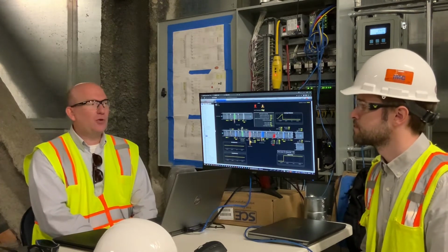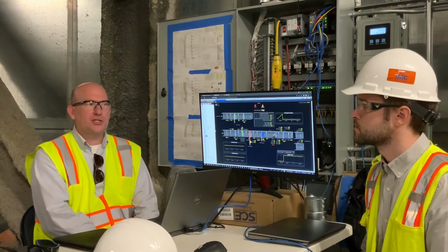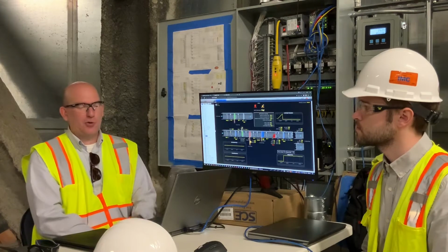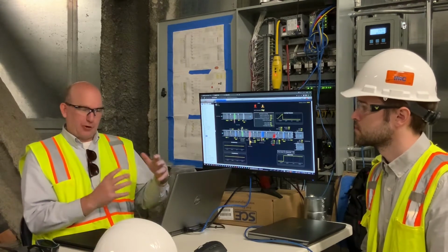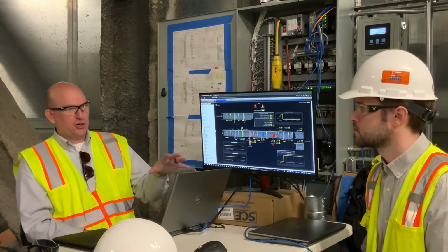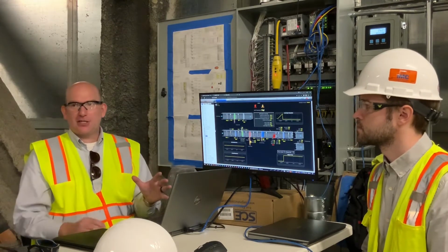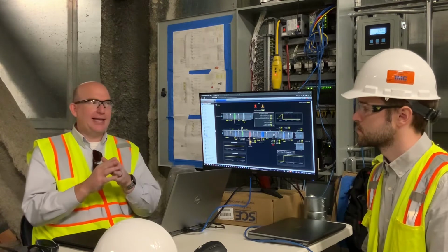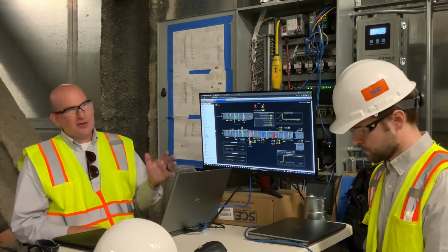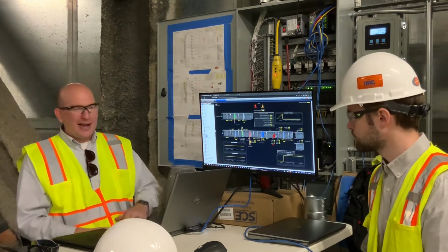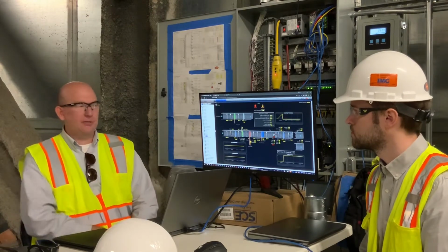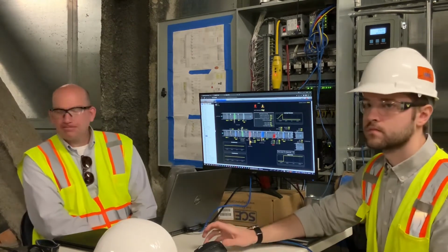But the thing we don't know right now is what conditions all the stuff down in the space is at. Because it's a blend of both Phoenix valves and pressure dependent VAVs, we do have a static discharge reset. If it was all Phoenix stuff, we would have one number, we'd try to hit the lowest possible to make sure all the valves will work, and we'd be good to go. But because we have the pressure dependent stuff, we might have to ratchet the fan set point up and down to accommodate depending on the position. Same thing with the exhaust too.